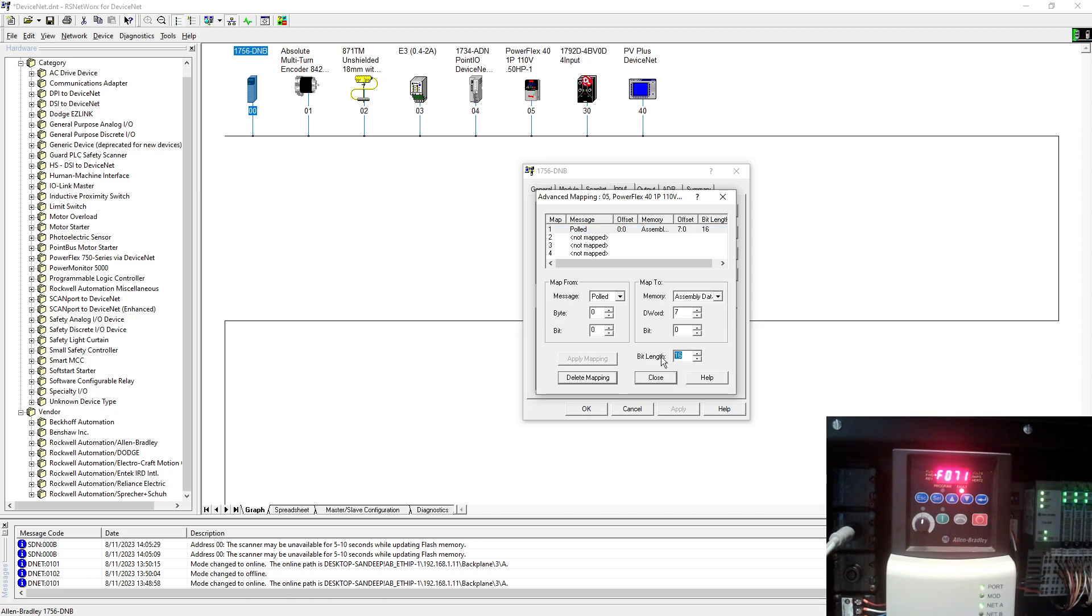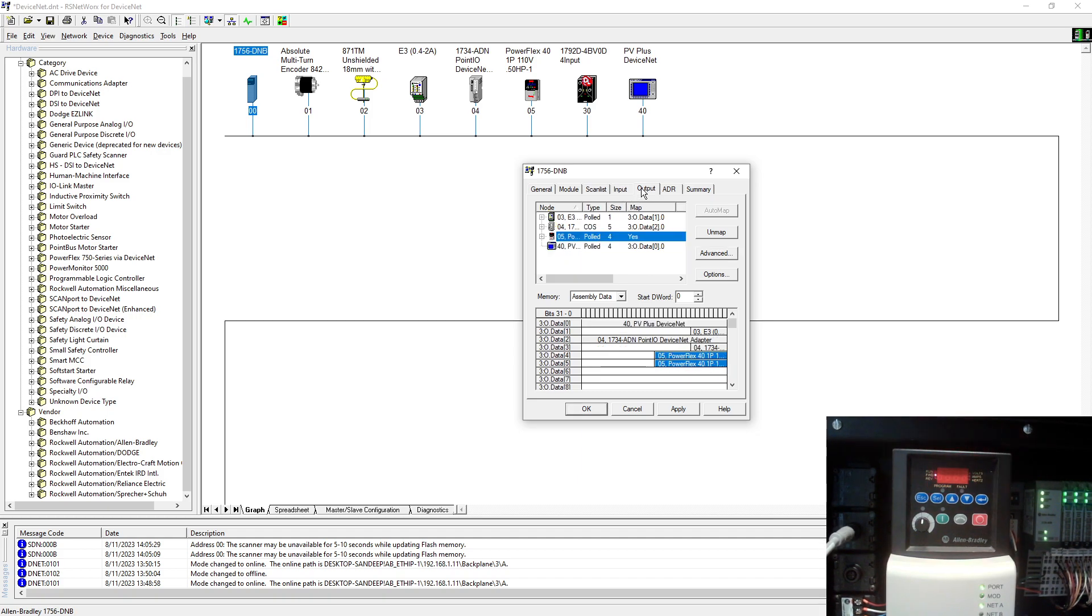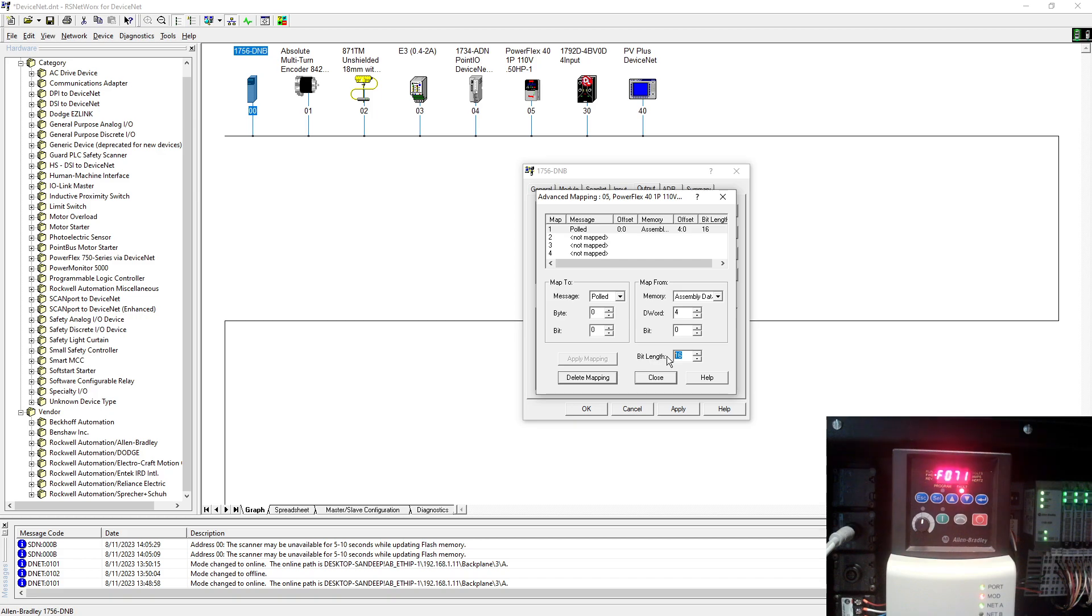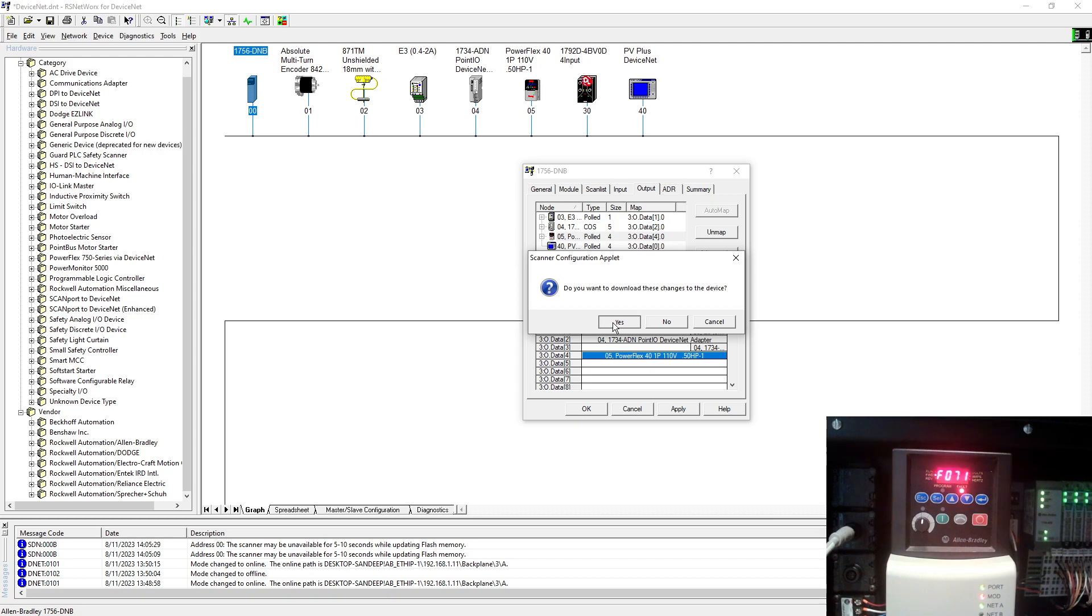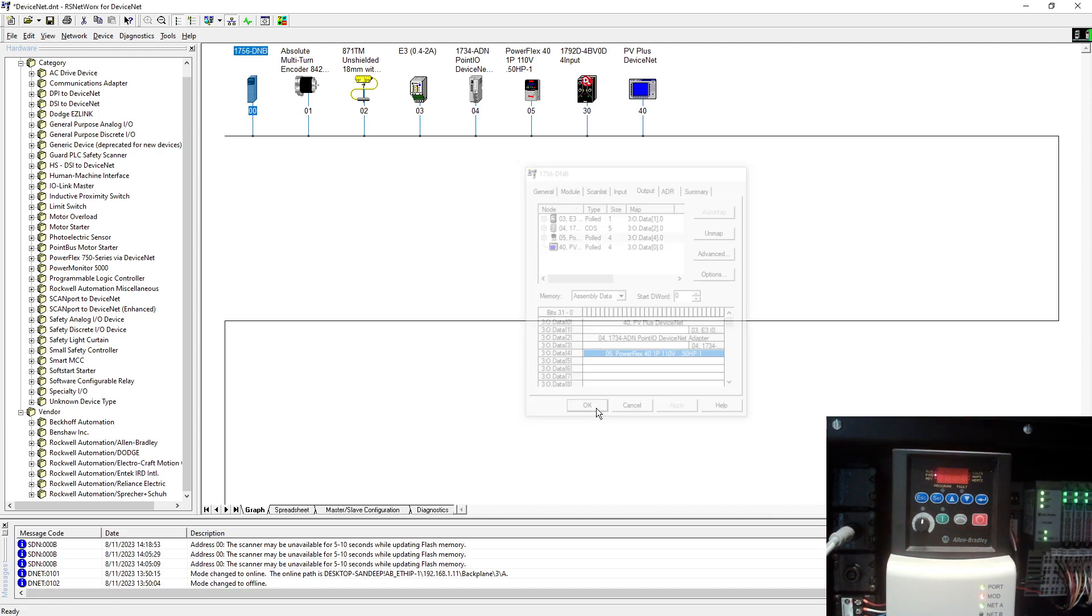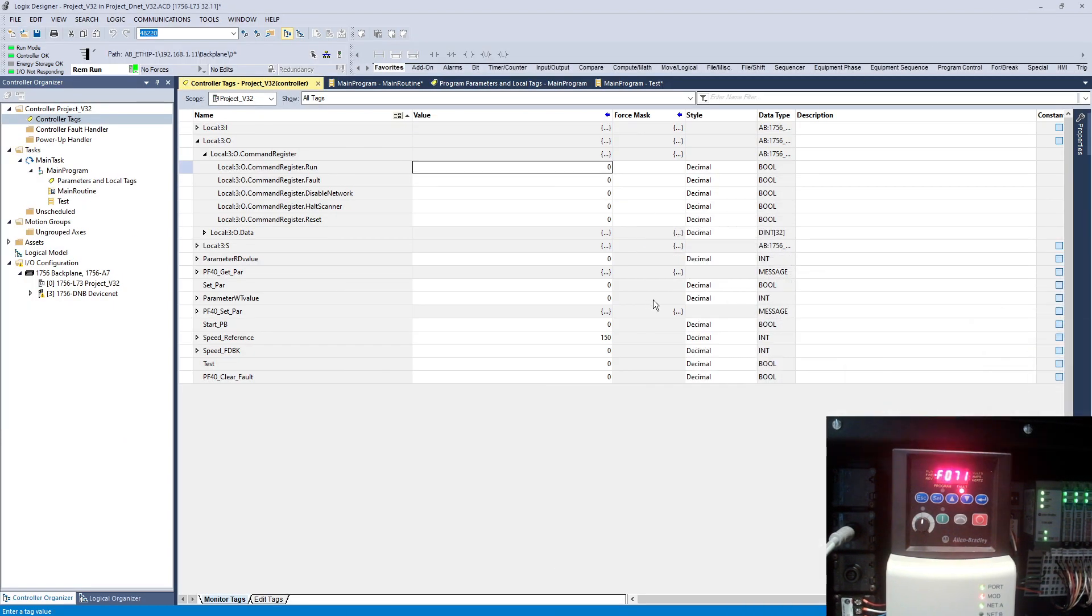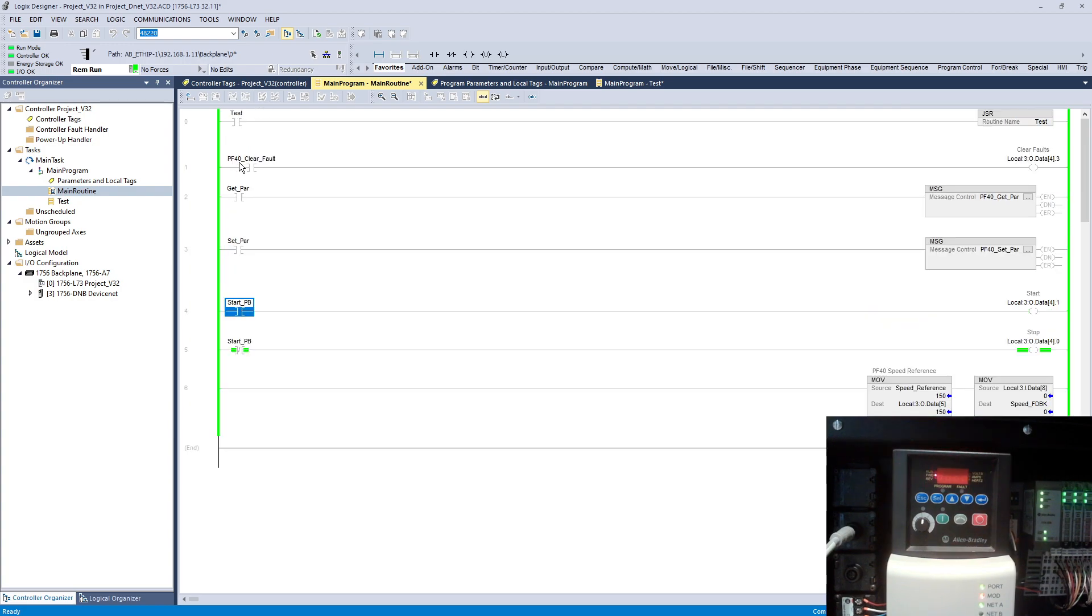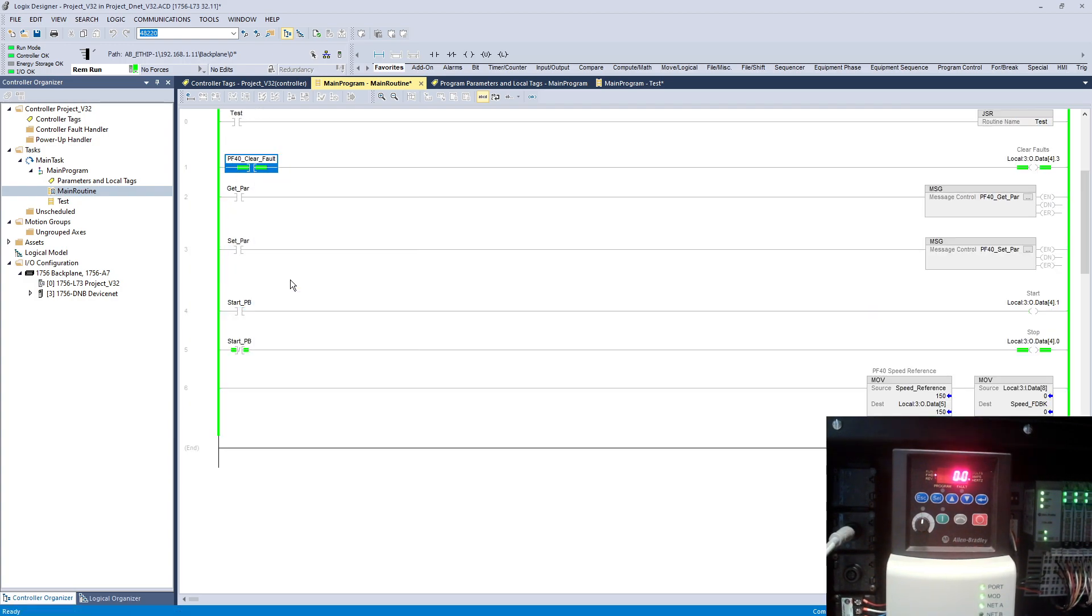Come back here, use 32, apply mapping, close. You can see all 32 are here. Same, let's do here advance, delete this and make this one 32 the way it was before. Apply, yes, download into my scanner. Now let's put this one in run mode and clear the fault on the VFD. Fault is cleared.